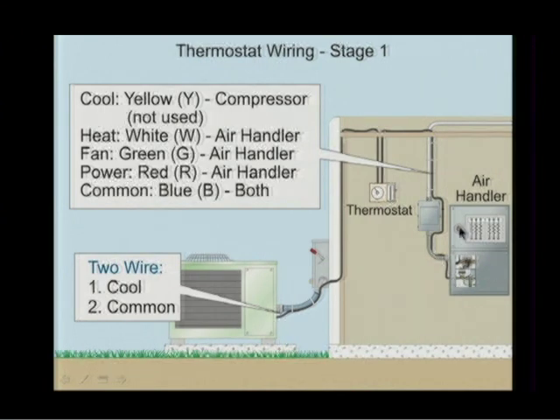Then I have the blower. That'd be another relay. That's 2 wires. Then we'd show the transformer. Well, that's going to be primary 2 wires, secondary 2 wires. So I have 2 wires off the transformer, 2 wires from the heating relay, 2 wires from the fan relay, and 2 wires from the compressor relay. And somehow I got to get 2, 4, 6, 8. I think there's 8 wires. Somehow I got to get them together to the thermostat.